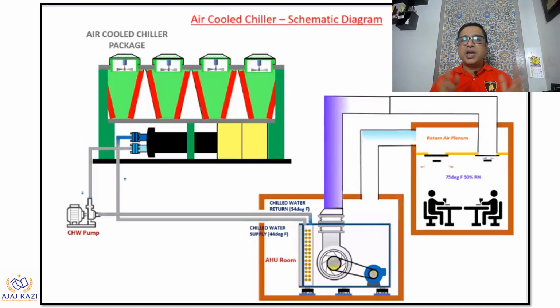As I discussed earlier, in a central plant we have a chiller, centrally located, which generates cold water, which is pumped into this equipment that I am explaining, called the air handling unit. You can see over here, this equipment is connected with a duct which supplies the cold air to the respective areas to be air conditioned. From that same area, I pick up the hot air as return air. It comes back to the same unit and flows over the coil, which is cold because of the cold water supplied by pumps from the chiller. So this is how it works.